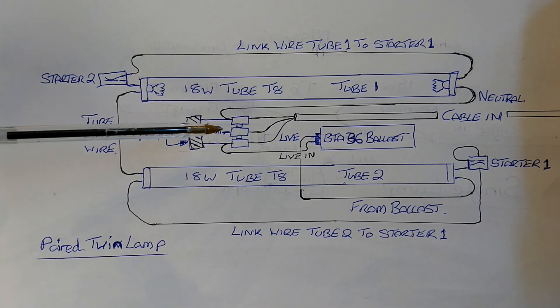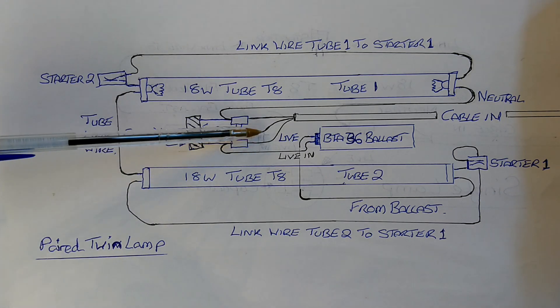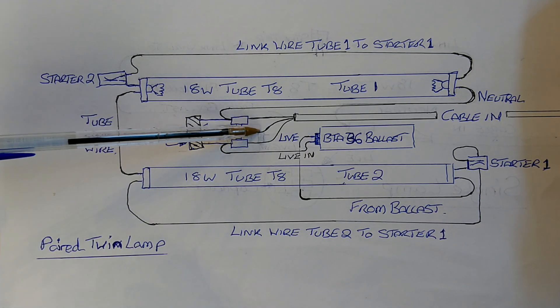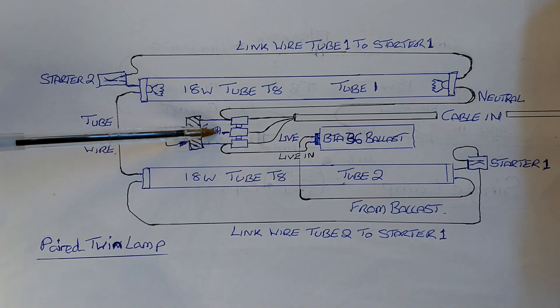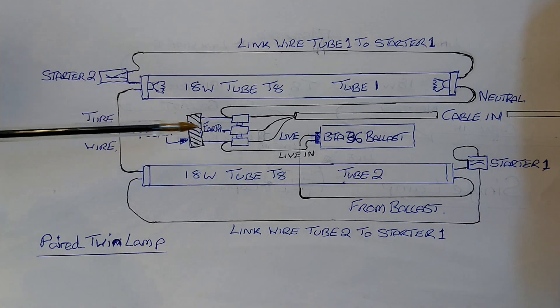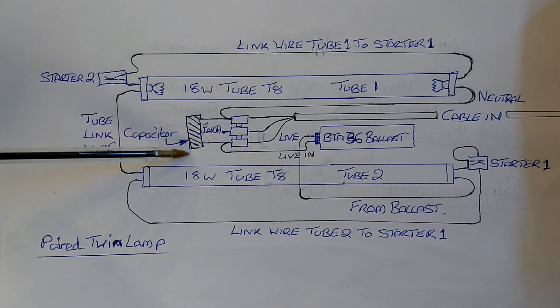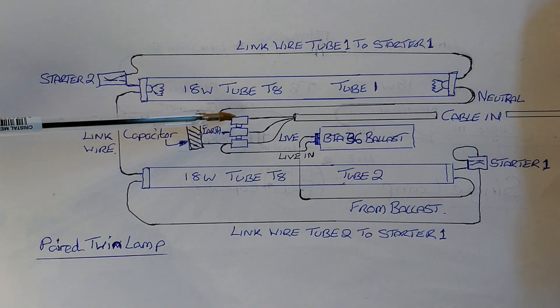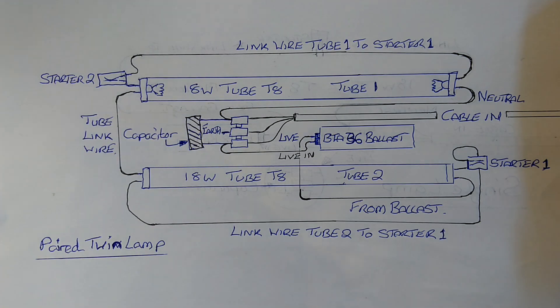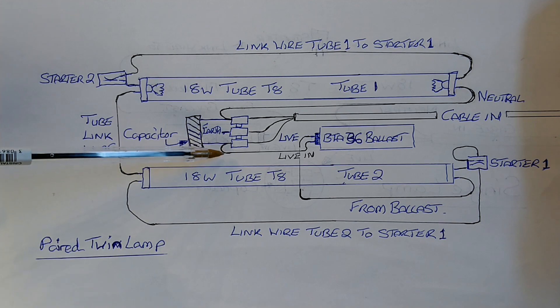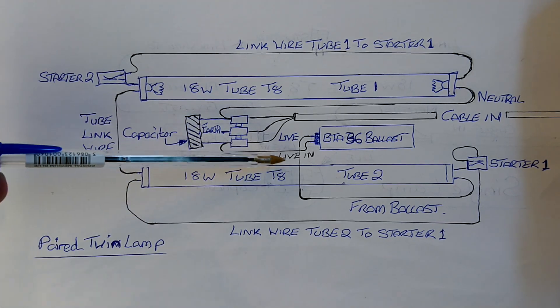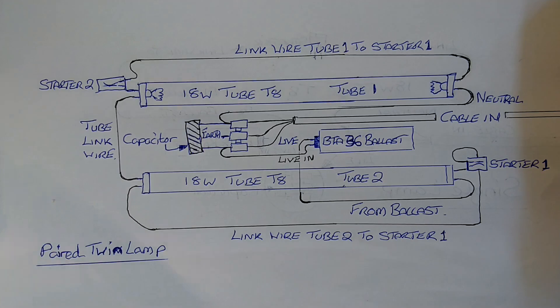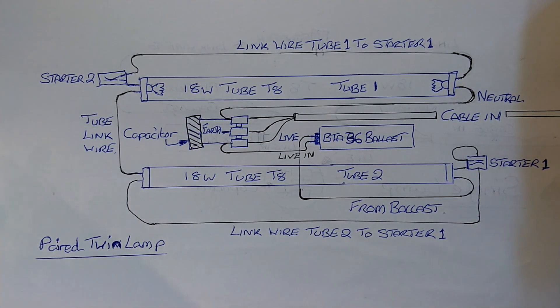So again we'll start with cable in, and this time it comes from this side. And again we've got live, neutral and earth. Earth is connected again to the body of the light fitting. We have a capacitor again, a small one which is bridged between neutral and live. The live wire comes out from the connector block and goes straight to the ballast. This ballast is a 36 watt ballast.